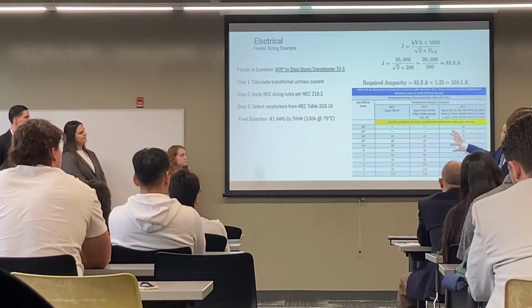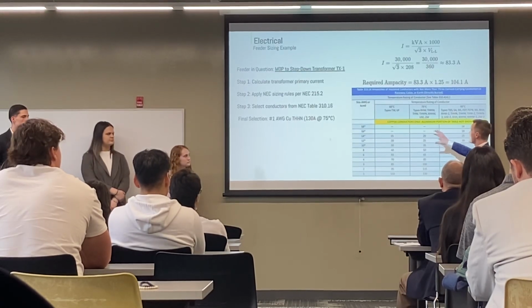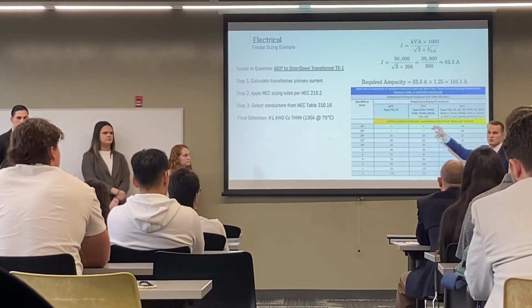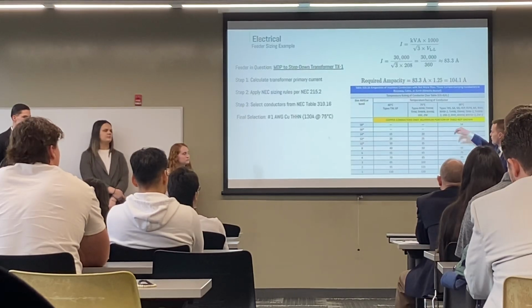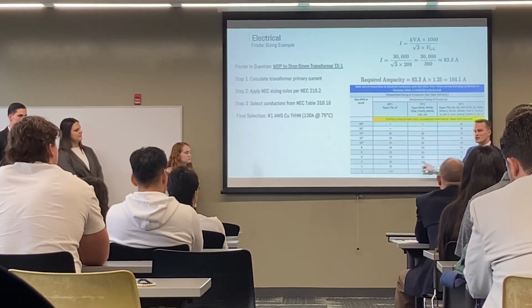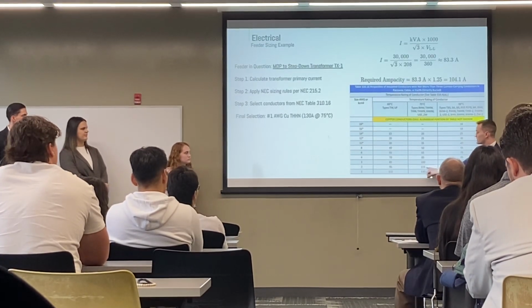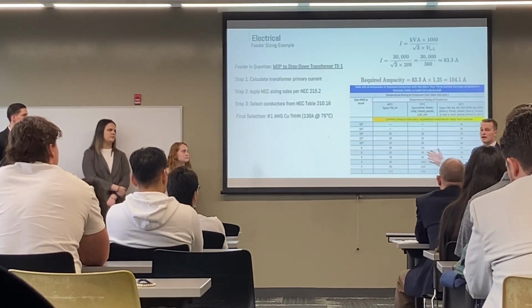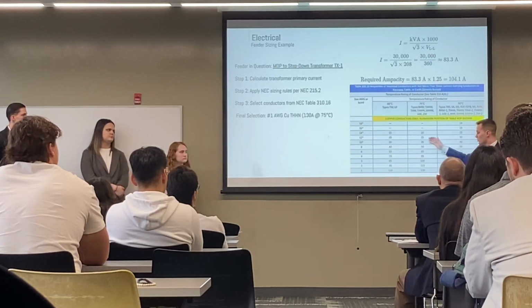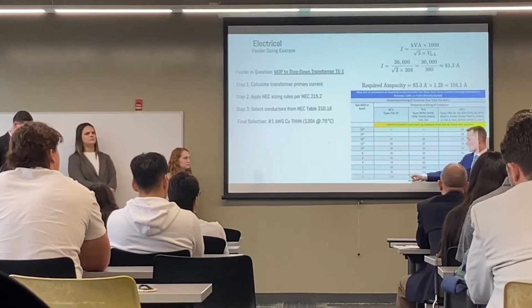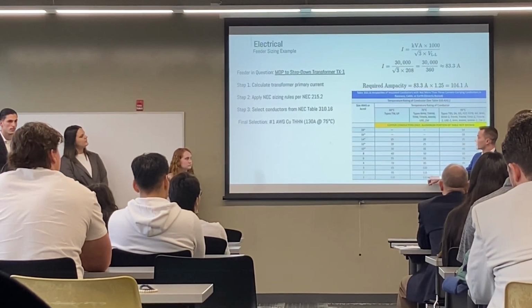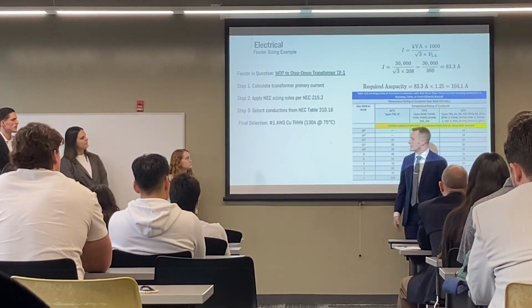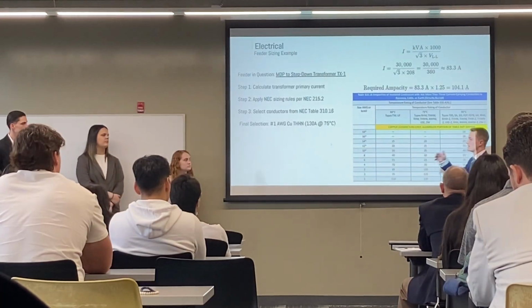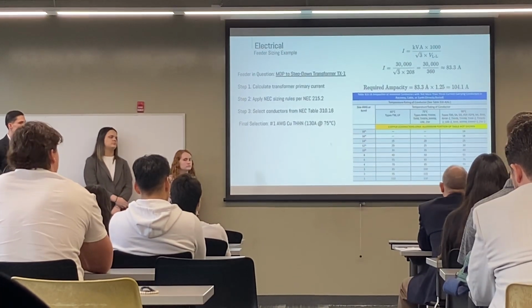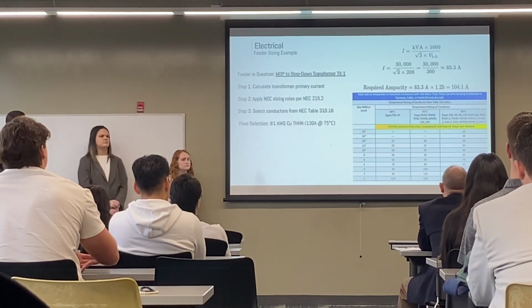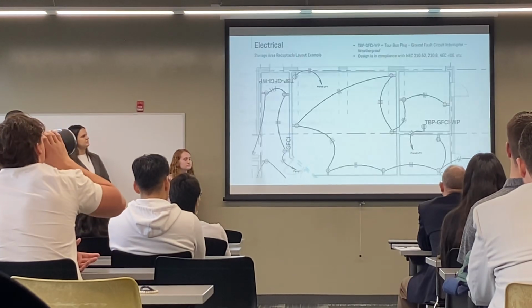Then we come over to NEC Table 310.16, and we're going to use 75C, as that is what the panel terminals are rated for. We come down, and you see number 3 is only 100 amps, so that's not good enough. Number 2 would be for 115 amps, that would be big enough. But just for added safety, we're going to go down to wire gauge size 1, 130. And so your final selection is single gauge copper wire, THHN insulation, for 130 amps at 75C. And so now we're going to go to some receptacle layout.